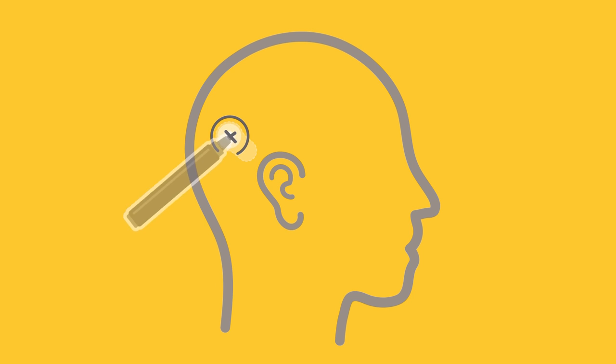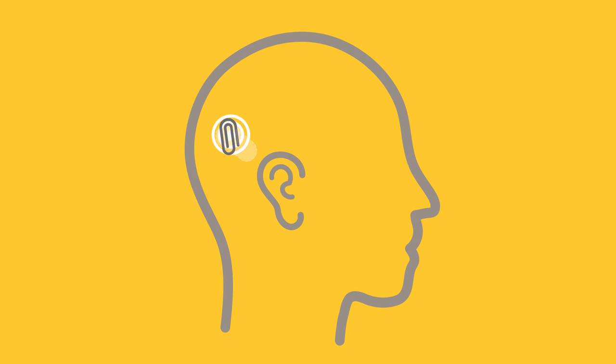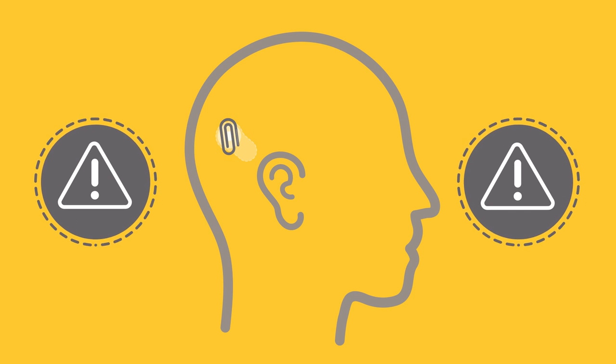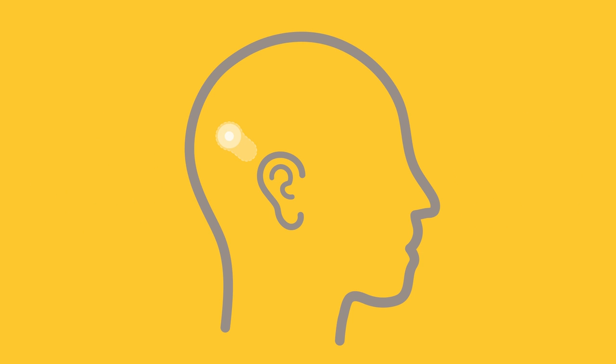If the location of the implant magnet has not been marked, it can be located using a ferromagnetic object such as a paper clip, as the object will be attracted to the implant magnet. Remember that ferromagnetic material must be removed before entering the MRI room.